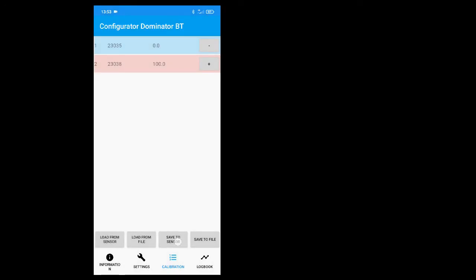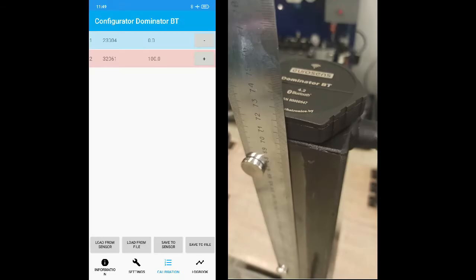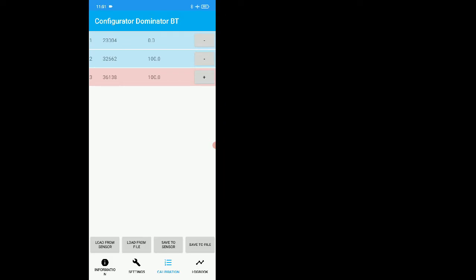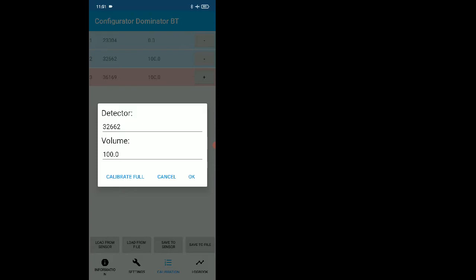Now you can calibrate sensor full. Immerse the sensor fully into fuel — you can use a special tube for this — and wait for the stabilization of detector values. Add a new row with the plus icon, open this row, and push the button Calibrate Full. Save the values to the sensor.